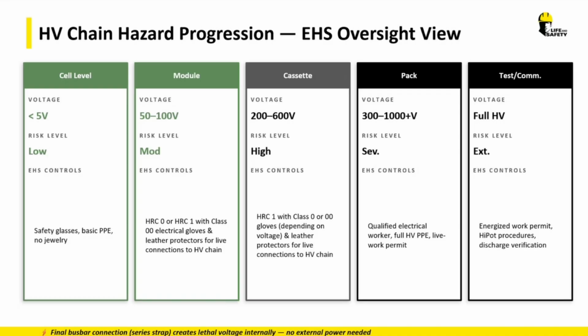All those things are must-haves. Just because you have an arc flash hazard -- meaning something detonated in front of you and you were exposed to heat, thermal energy, and thermal runaway -- doesn't mean you don't also have a shock hazard. A lot of folks miss that electrocution and shock by DC is extremely hazardous. So you have to train people who aren't normally qualified electrical workers to be familiar with this different kind of hazard, a direct current one.